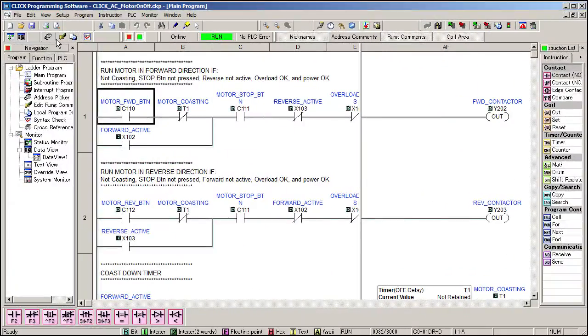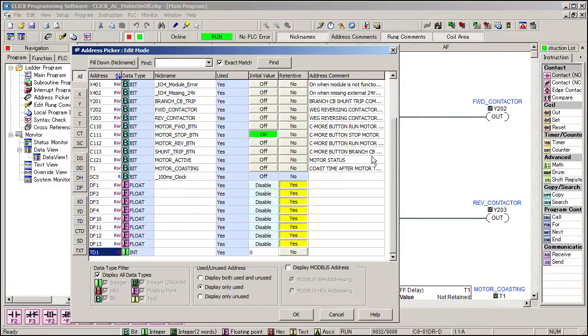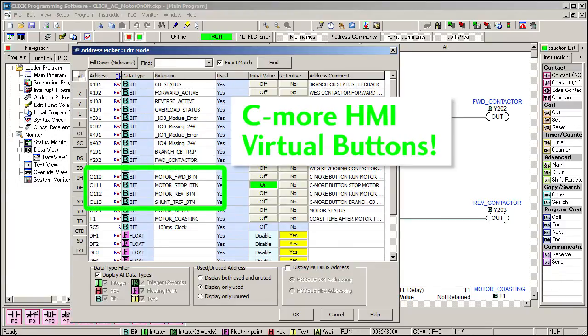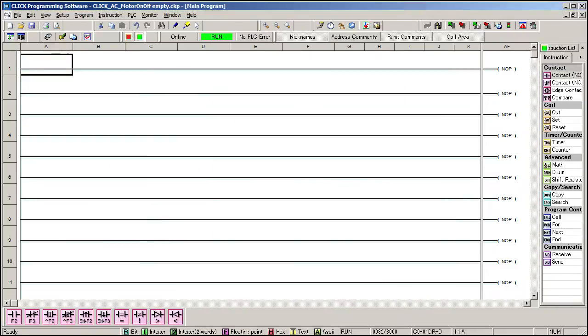I've already allocated some memory addresses and entered all the tag names to save us some time. You may notice there aren't any physical button inputs. That's because we are using a C-more HMI to control this system. So instead of looking at PLC inputs, we'll be using these memory addresses that are being updated when the user presses the virtual buttons on the C-more screen. The stop button is set to start active because it's a normally closed push button. OK, let's do it.